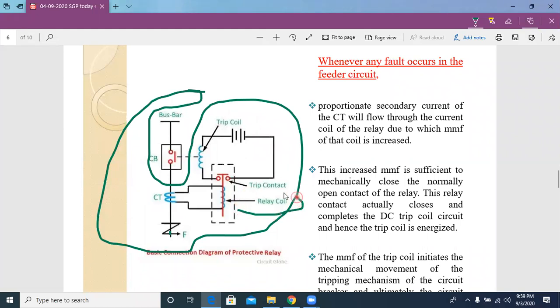Because of this relay coil excitation, the trip contacts are closed because of tripping action. When the tripping contacts are closed, this tripping circuit becomes like a closed circuit. Because of this DC source, current flows through the tripping circuit. When the current flows in the tripping circuit, the tripping coil is excited. When the tripping coil is excited, because of mechanical action, circuit breaker contacts are open. When the circuit breaker contacts are open, ultimately the entire feeder is isolated from the bus bar. In this way we can protect the bus bar when the fault happens in the feeder.